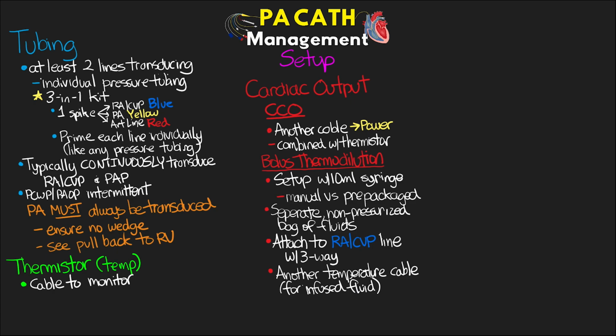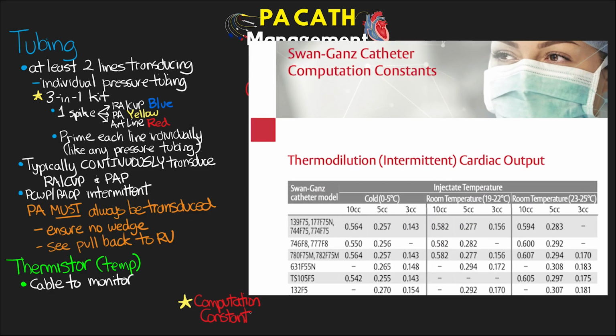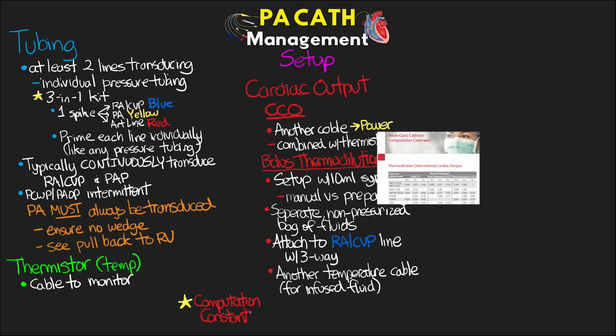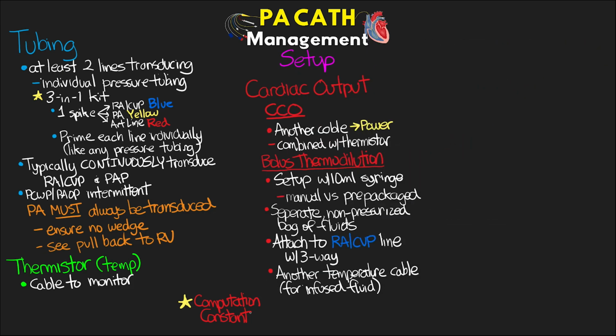Now, when we're doing the intermittent bolus thermodilution, it is important that you get the proper computation constant programmed into your monitor. So real quickly, I'm just going to show you an example of part of a chart that has some of the Edwards swans with their different models and associated computational constants. So what this is, it's actually a number that adjusts the algorithm in the computer that's used to do the calculation for cardiac output. The way that it does this is it's looking at the thermodilution curves and the time it takes to change temperatures, and this is going to be affected by the size of the catheter and how quickly or slowly you're able to actually infuse fluid.